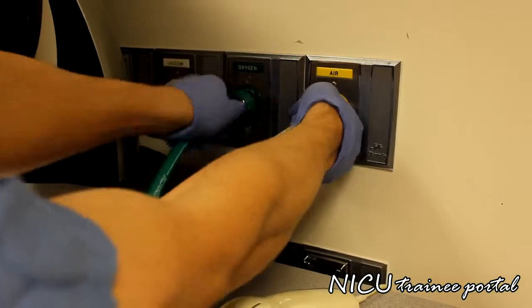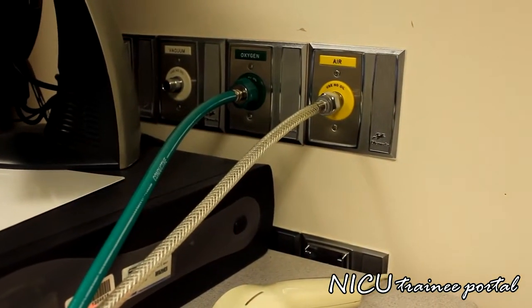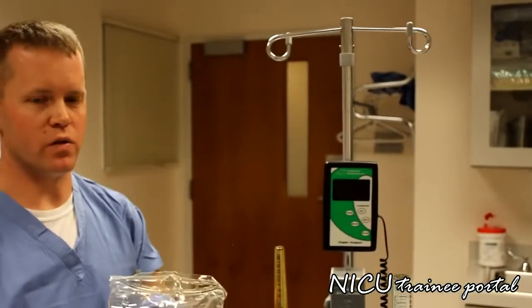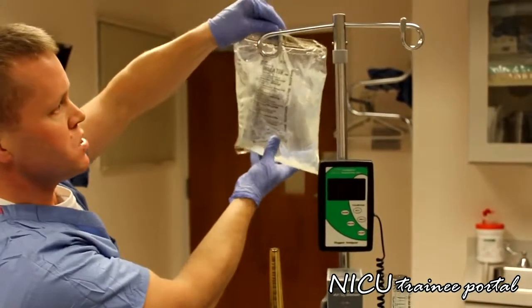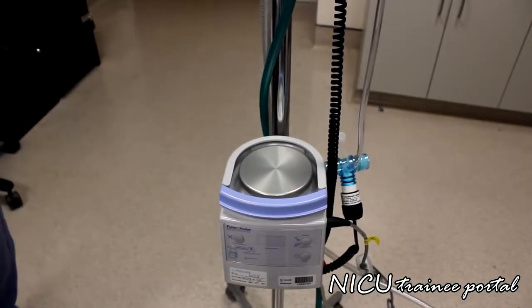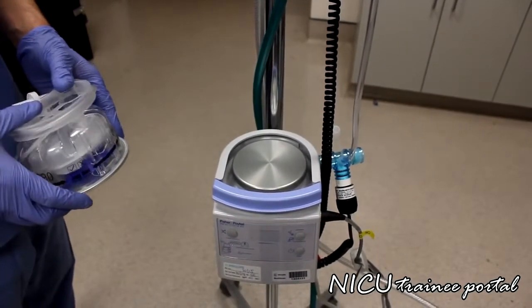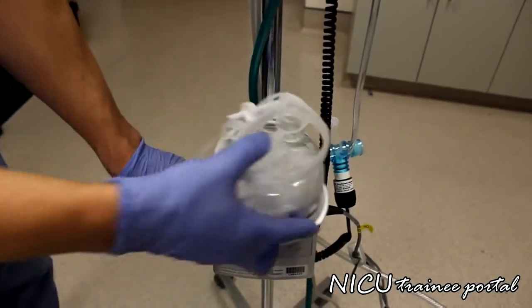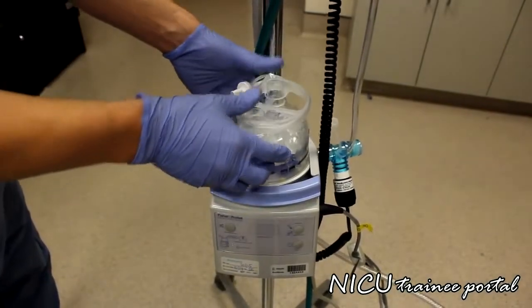With our gas sources connected, we will now plug in the heater to a power source. First, we are going to hang our water bag right on top of the IV pole. The next component is the water chamber connected to the humidifier — in this particular model we depress it, slide it under the collar, and you will hear it pop in.